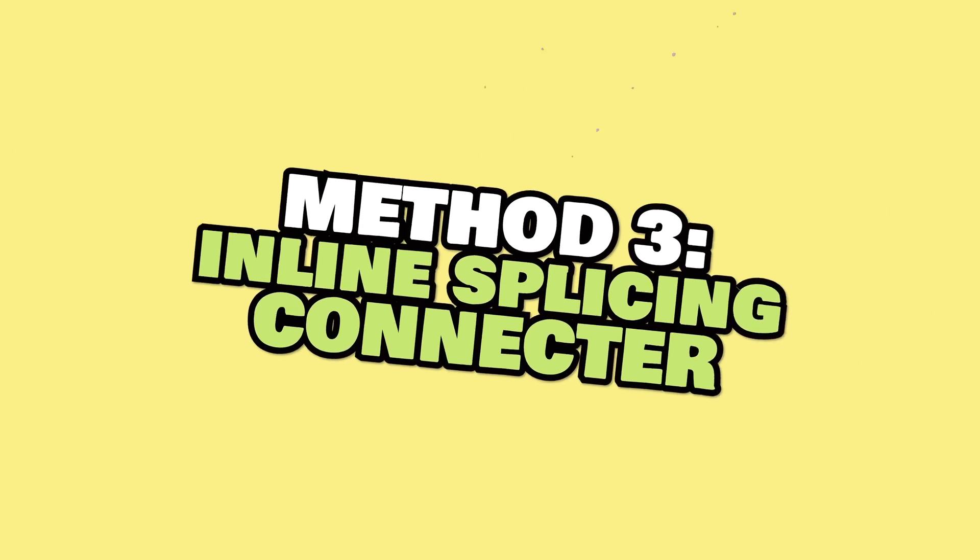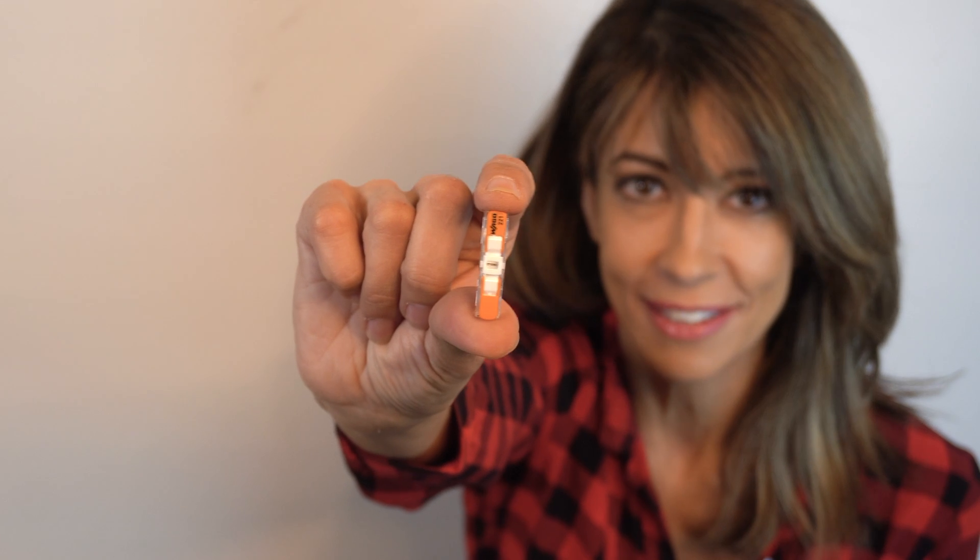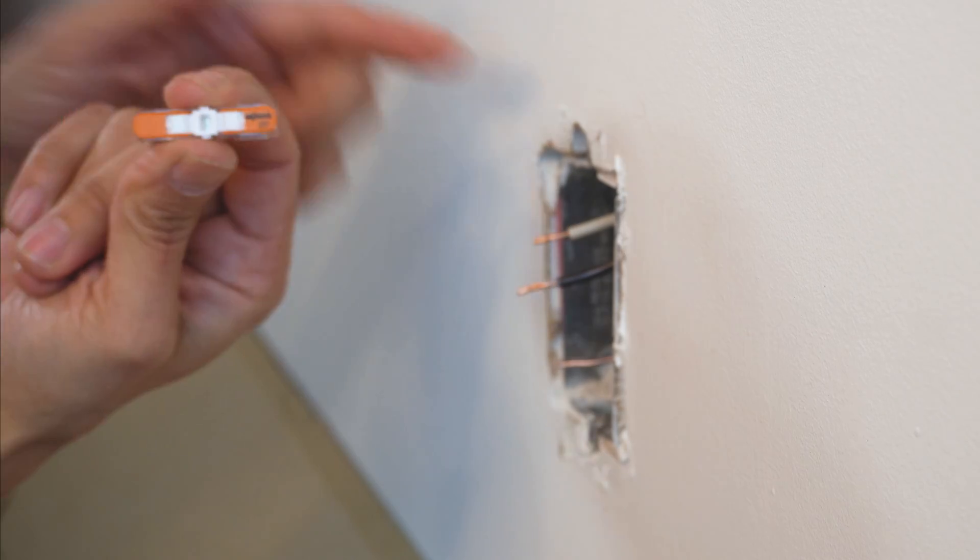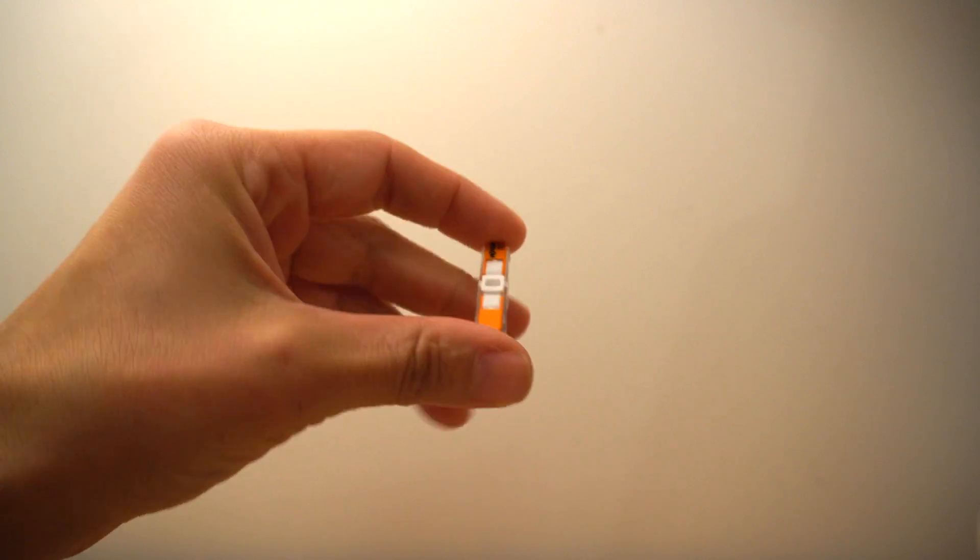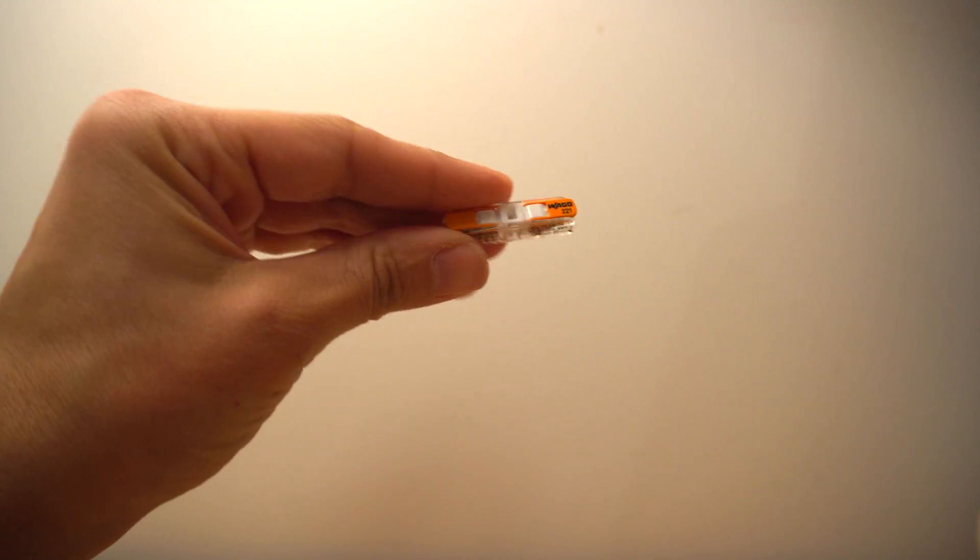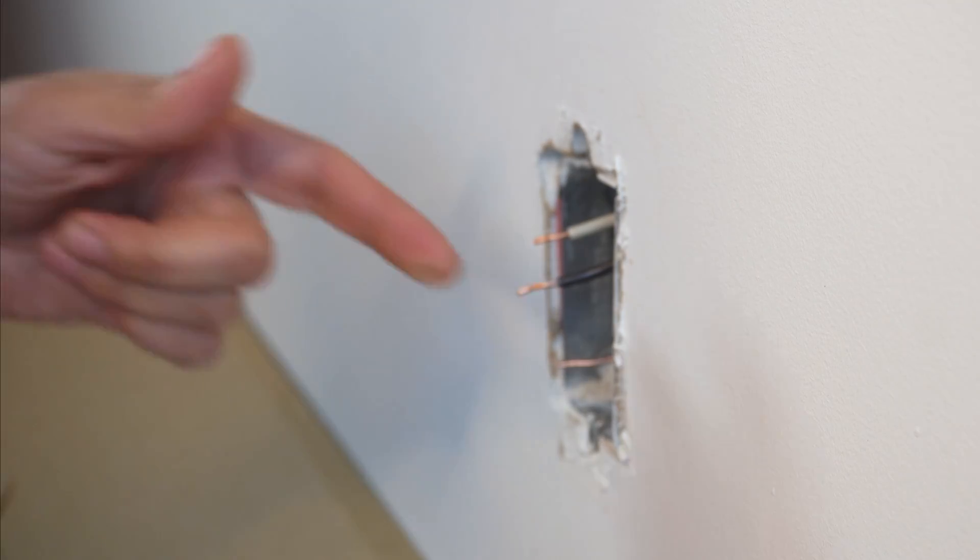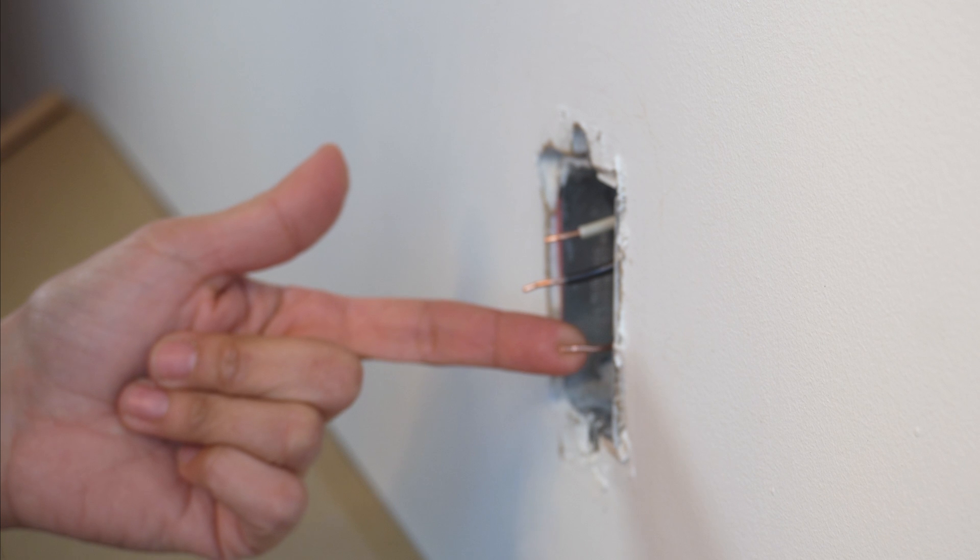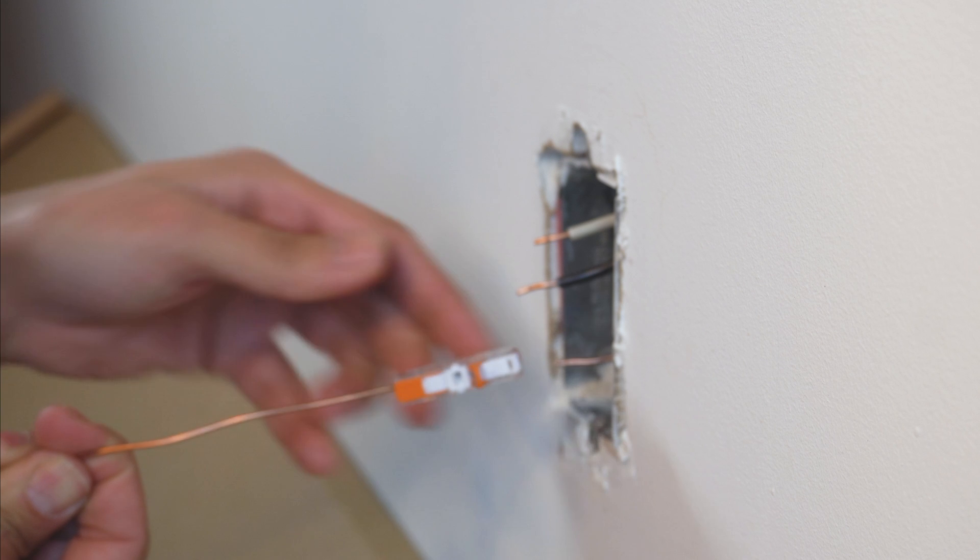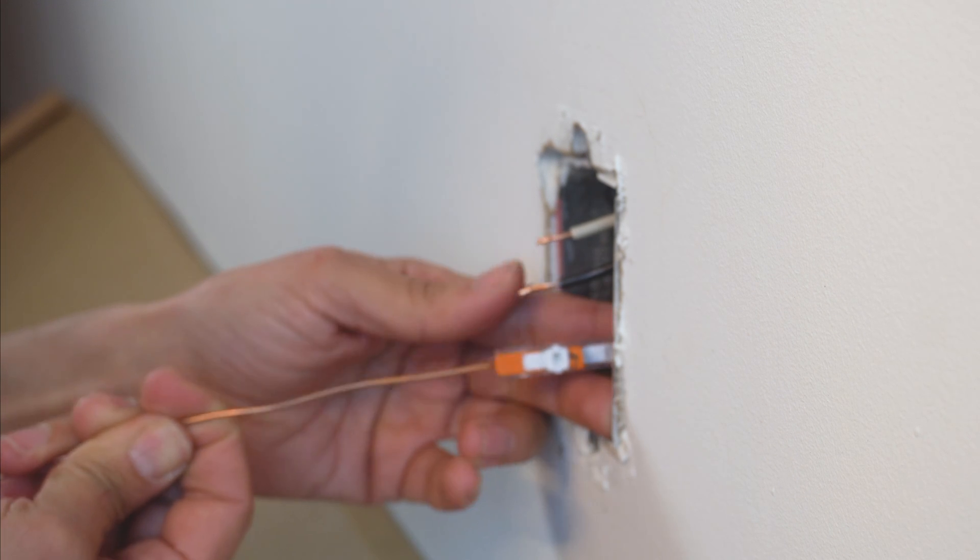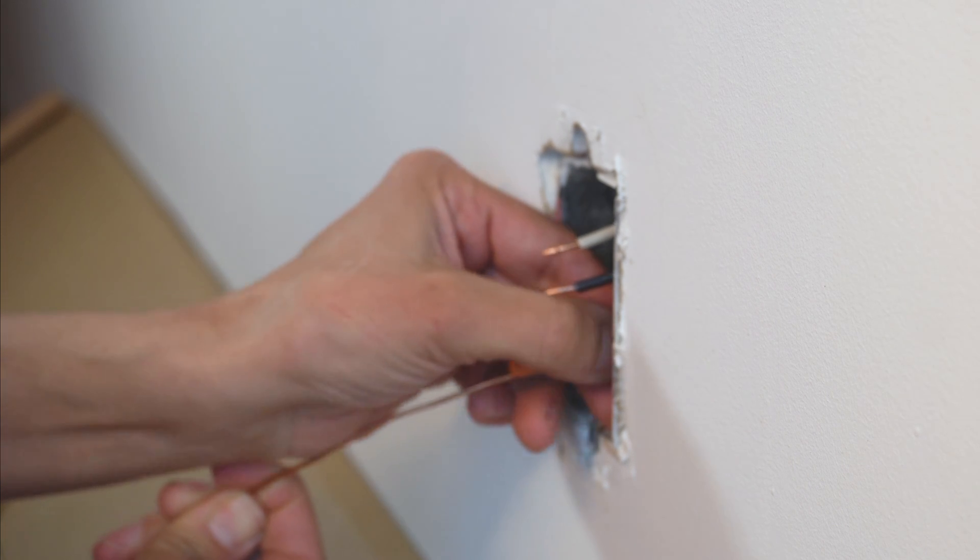Method number three is the WAGO inline splicing connector. So to fix these wires, we are going to use the WAGO 221 lever connector. Now, it's really important to note the white part here on the front of the lever. That's critical. We'll get to that in a second. We're going to start off with our ground wire and I've inserted the inline splice onto it. I've left the lever door open and I'm going to push that in all the way until it meets resistance. And then I'm going to close the lever.